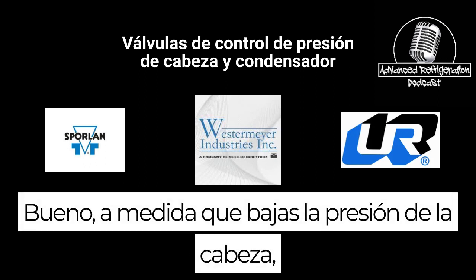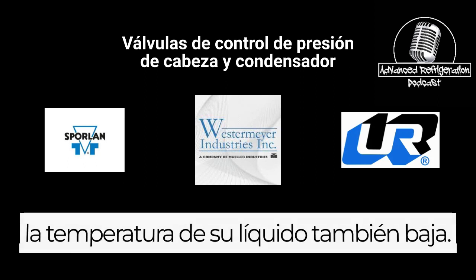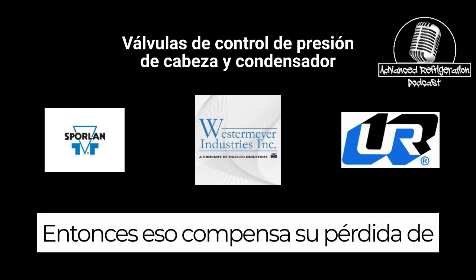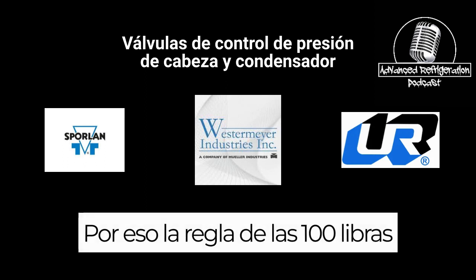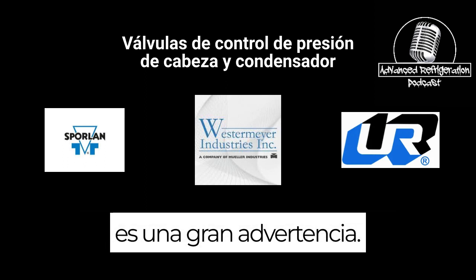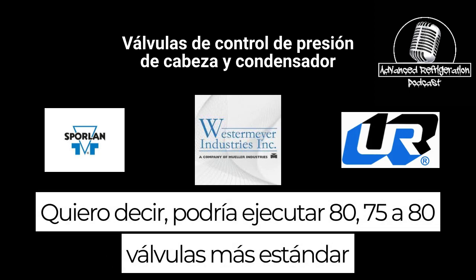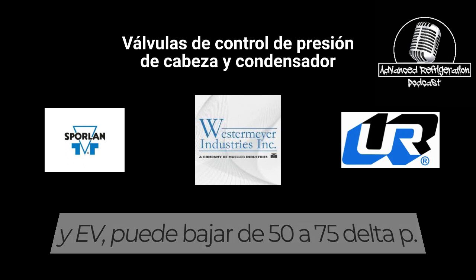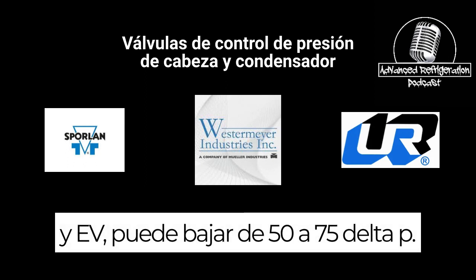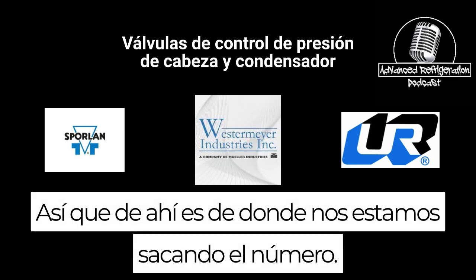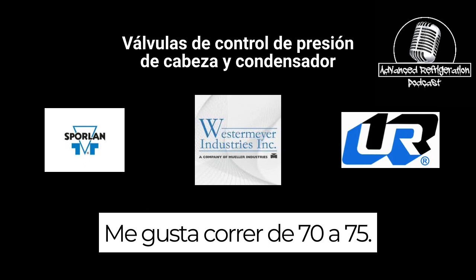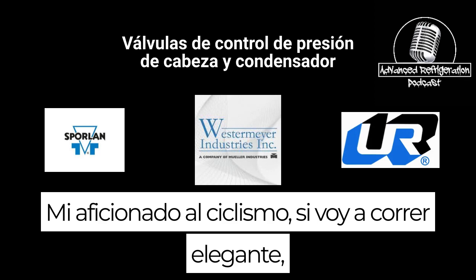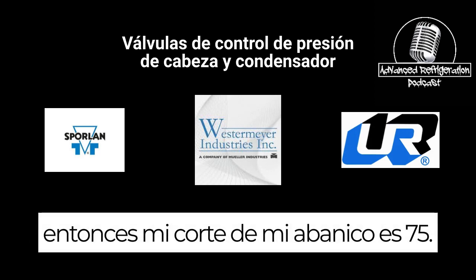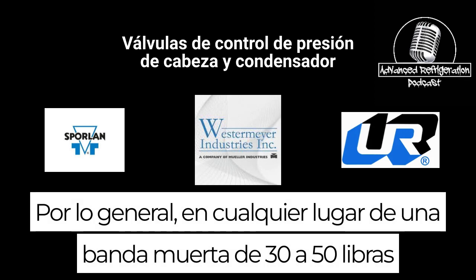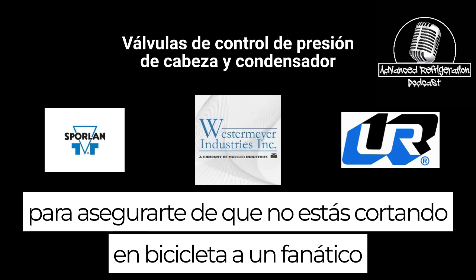Well, as you lower your head pressure, your liquid temperature also comes down. So that offsets your loss from your delta P in most cases. So that's why the 100-pound rule is so much of a caveat. I mean, you could run 75 to 80. Most standard valves and EEVs, you can get down to 50 to 75 delta P's. So that's where we're coming up with the number from. I like to run 70 to 75 on my fan cycling if I'm going to run fan cycling. So my cutout of my fan is 75, usually with anywhere from a 30 to 50 pound dead band to make sure you're not short cycling a fan on a single unit.